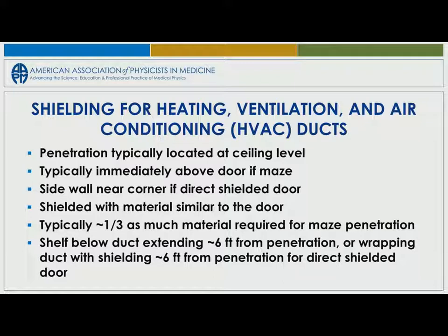If you don't do any calculations at all, keep in mind that you put roughly a third of what you have in your door around your HVAC penetration. So if you've got 6 inches of lead in the door, you put 2 inches of lead around your HVAC duct. If you're going to do the shelf method, you want to extend it at least 6 feet from the surface into the room.